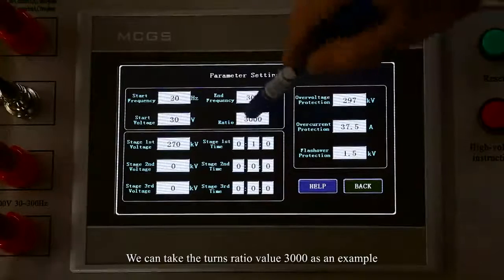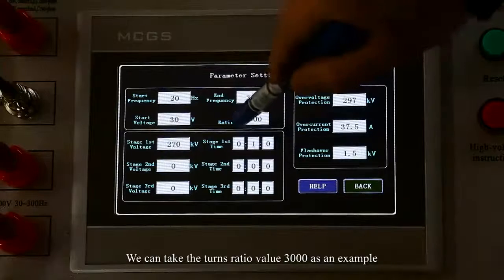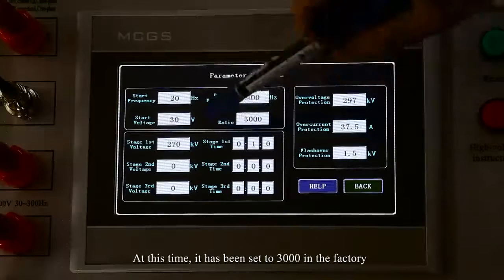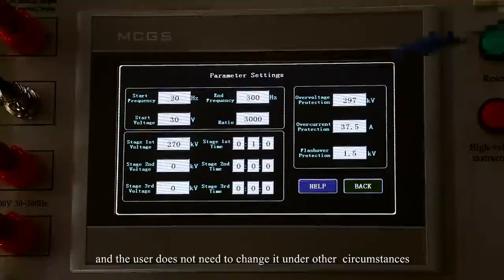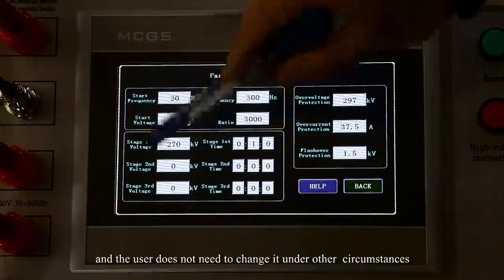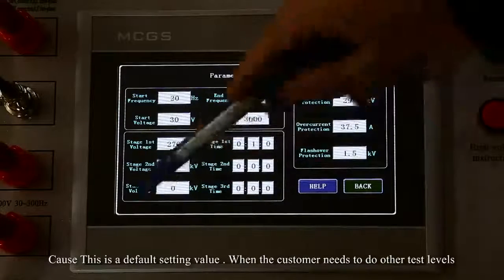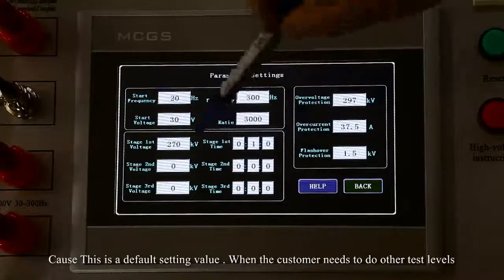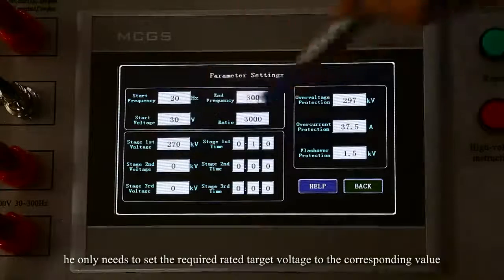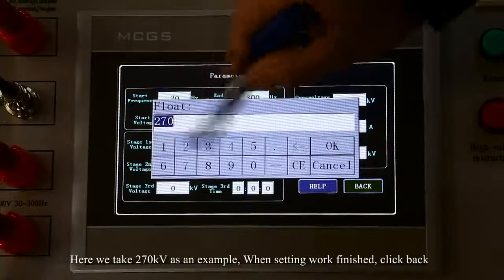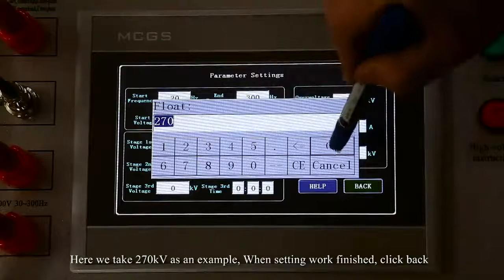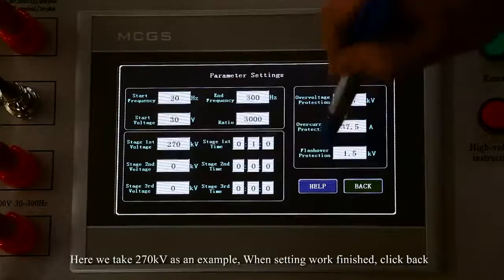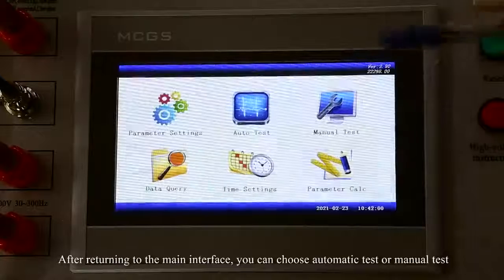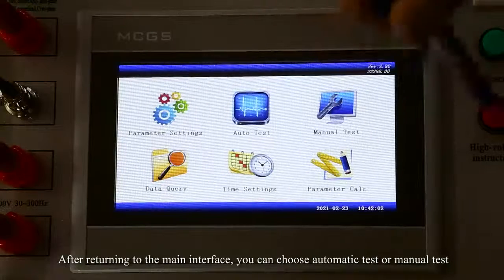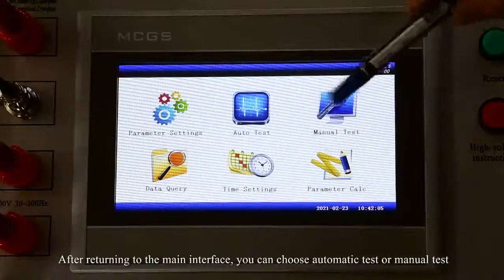We can take the turns ratio value 3000 as an example. It has been set to 3000 at the factory, and the user does not need to change it under other circumstances, because this is the default setting value. When the customer needs to do other test levels, he only needs to set the required rated target voltage to the corresponding value. Here we take 270 kV as an example. When the setting work is finished, click back. After returning to the main interface, you can choose automatic test or manual test.